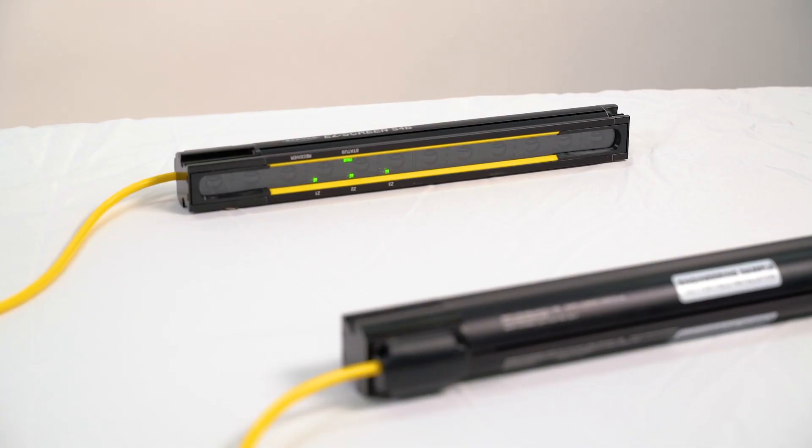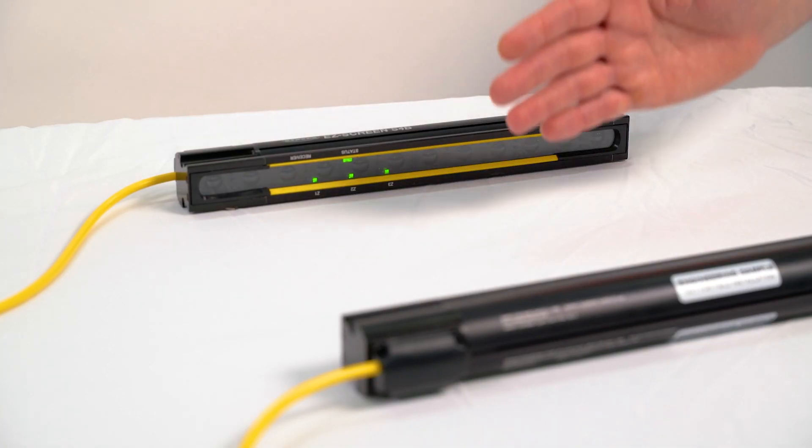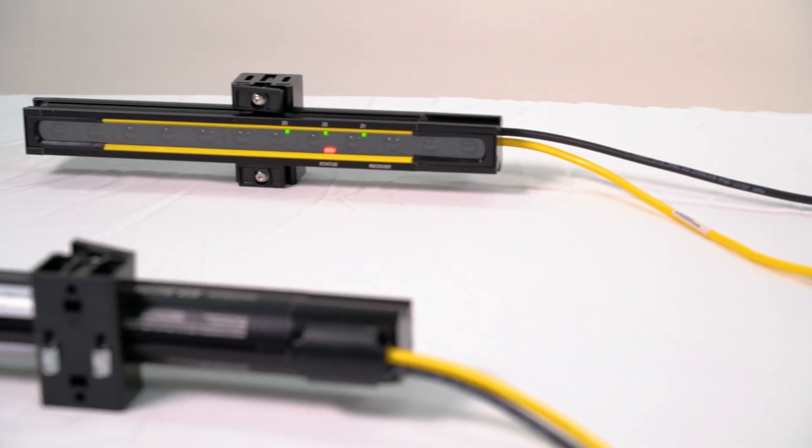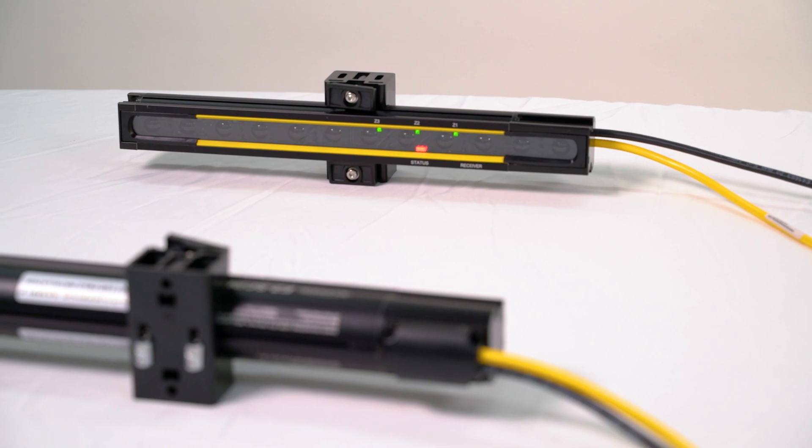You may test to ensure that the communication between curtains is functioning properly by blocking beams on the cascaded curtain. The status LED will turn red on the unit that was blocked as well as on the first receiver in the chain.